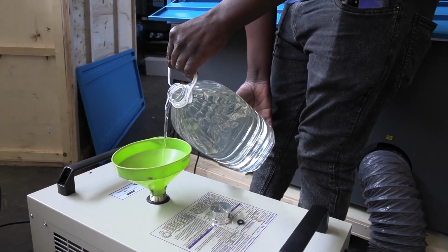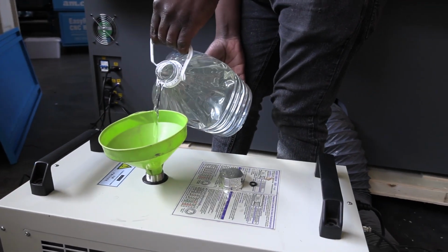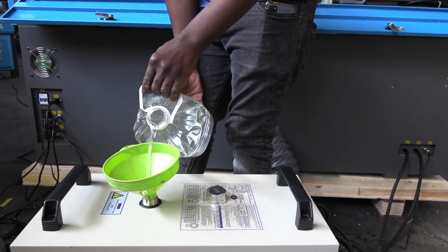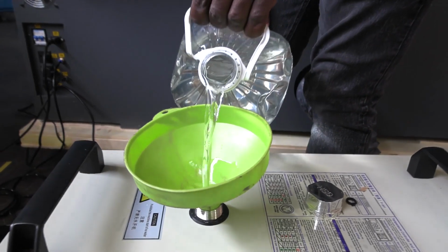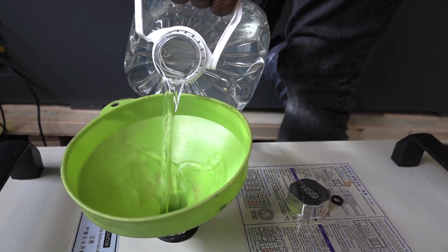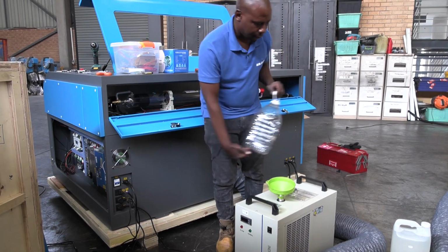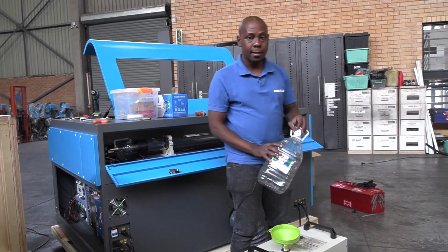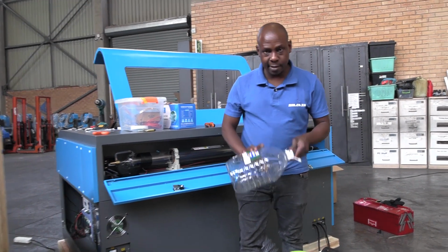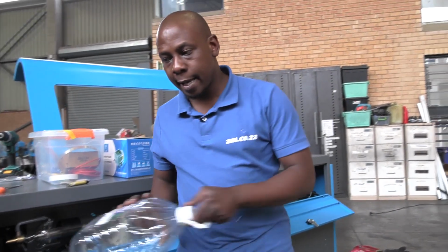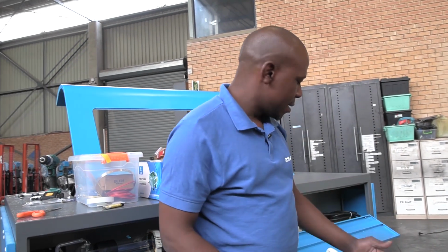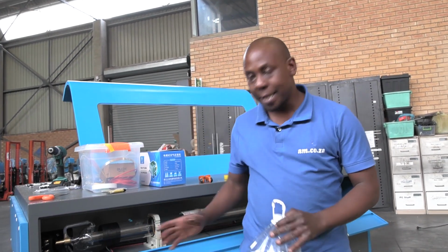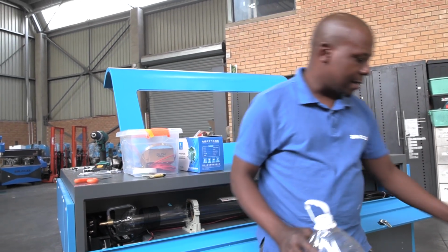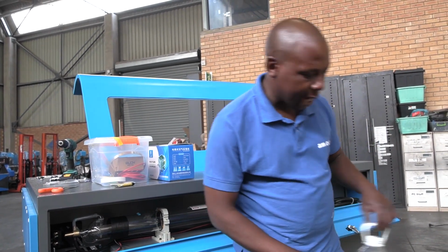So with this model of the chiller, it may take give or take 8 liters of water. So firstly, pour in your first 5 liters of water only, and then proceed to switch on the machine and also switch on the chiller, letting the water run through out of the chiller into the tube, and then you can fill in the remainder, checking with the gauge at the back.